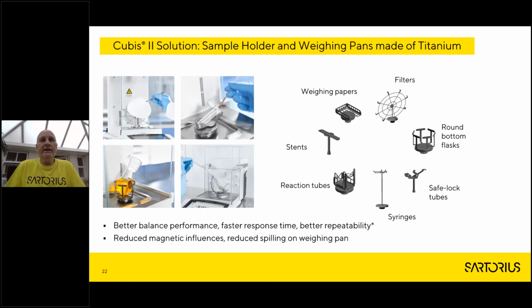In addition to this, we have nowadays many sample holders to hold different tare vessels. So we're talking about stents for stent weighing, weighing papers, weighing boats, weighing filters, so 37mm filters, 90mm, 110mm, round bottom flasks, safe lock tubes, syringes, reaction vessels and reaction tubes. This gives us more stability, better handling process, faster response time, better repeatability, and therefore a smaller minimum sample weight. It also reduces magnetic influences and reduces spilling in the weighing pan.